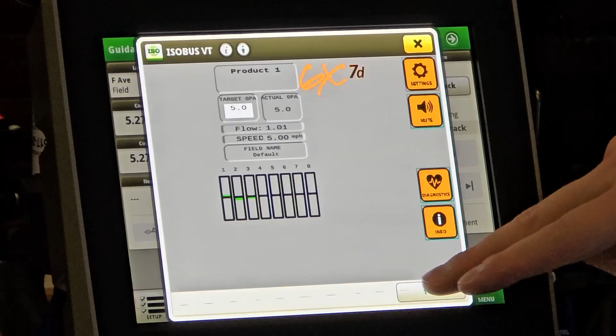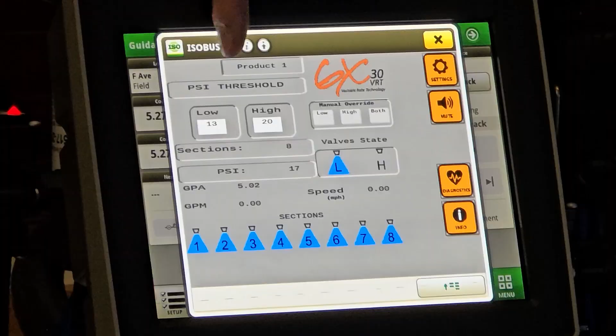I'll show off that GX30 real quick. So what this GX30 does is there's a pressure transducer on the system. Depending on what your pressure is at, whatever thresholds you have in there, if you were to exceed either the high end or low end pressure, the valves will adjust.